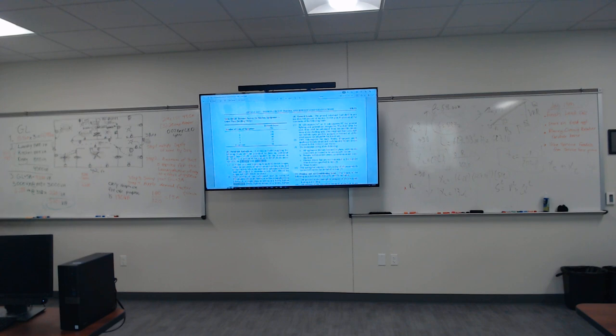So for the neutral wire, if you look at number three, it says apply the demand factor. We already figured out that 7,734 is the VA for the line. And for the neutral, it says the neutral VA for number three is going to be the same. When you go down to number four, no, I apologize, I messed up, my bad. Number three is a 5201 for the VA, and the neutral is the same size. So number four, we figured out 7,734. But let's go down to number five.